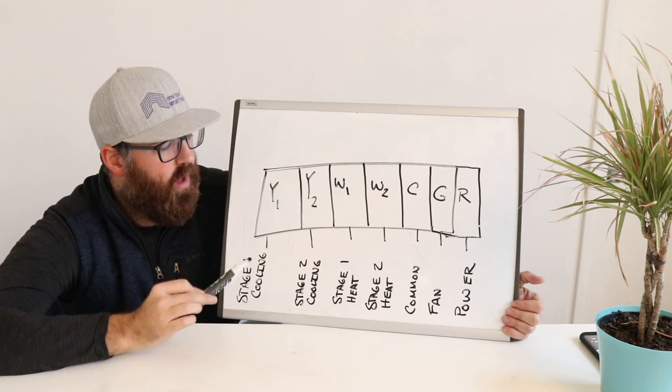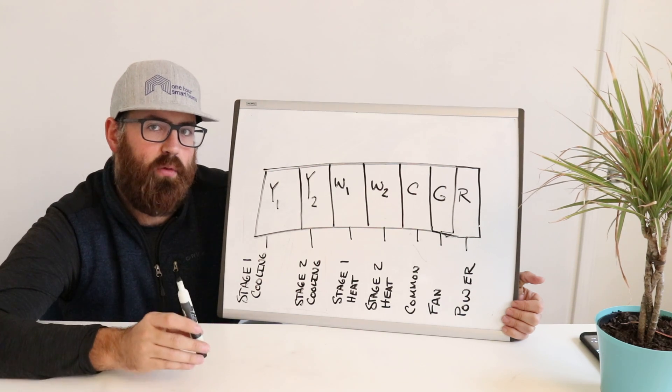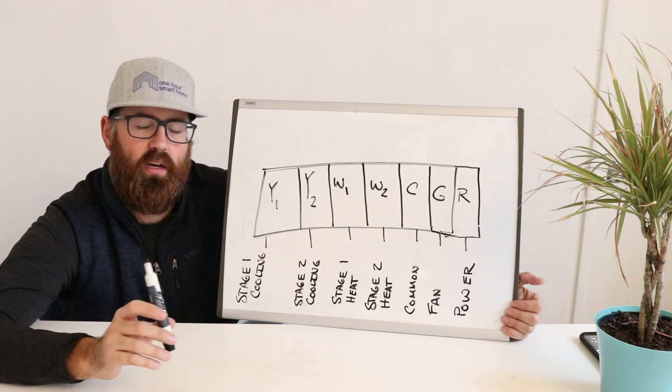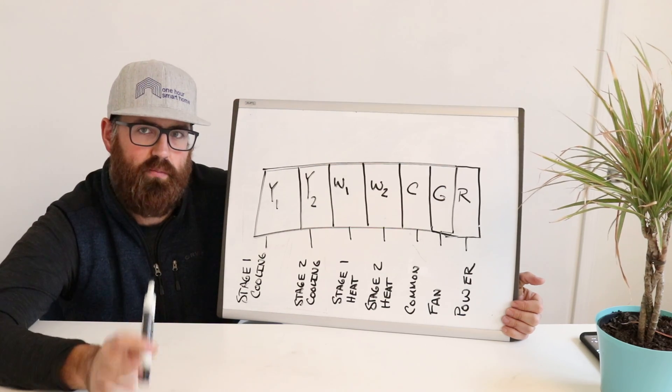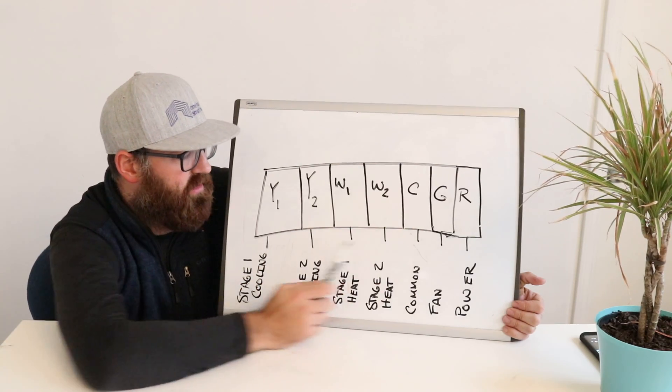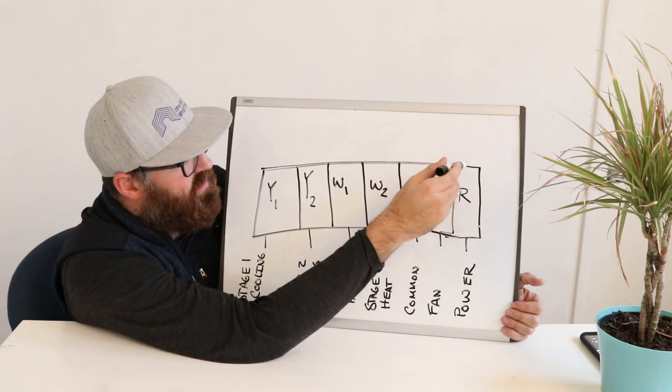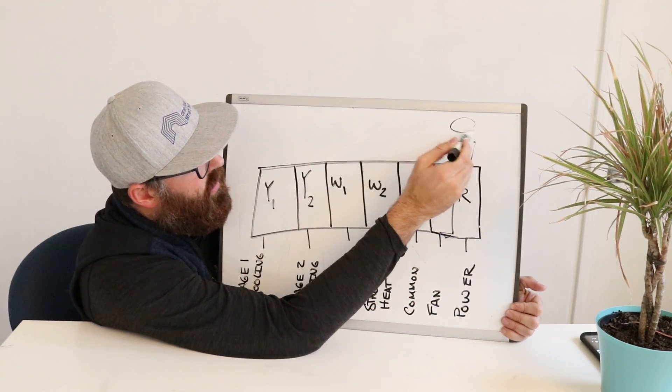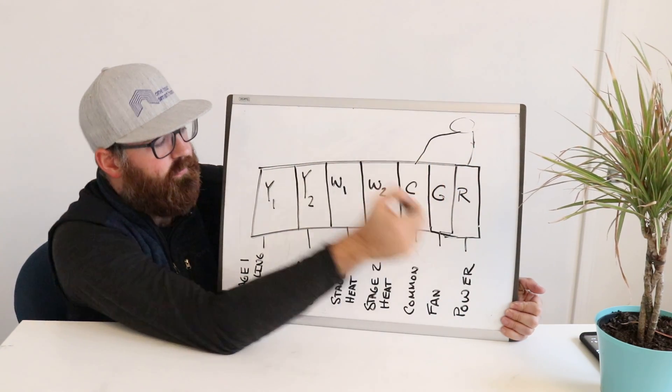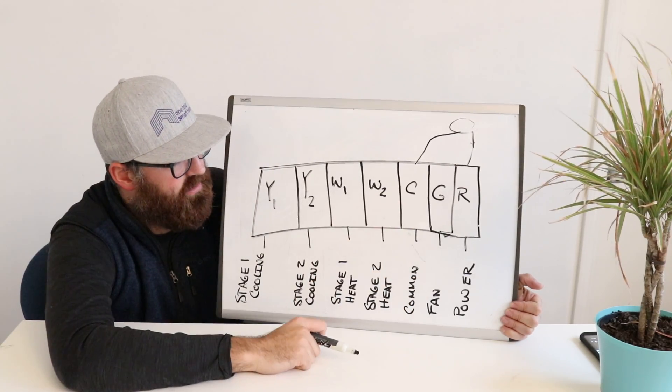Why do you need that? Well, because a C wire and an R wire allow the circuit to be completed so that your thermostat can connect to Wi-Fi. It can display its nice beautiful display that uses a lot of power without triggering any one of these other stages of heating or cooling to complete the circuit. So what this allows is a continuous circuit to your thermostat from the R wire to the C wire and allows it to be powered without triggering any of these other things.